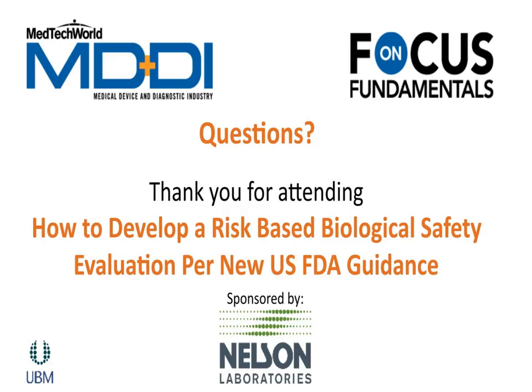Okay, so our next question for you, Audrey, is, I thought Thor said that changes in geometry alone would still require a couple of tests, like sensitization and hemo. Wouldn't this apply to the shorter catheter? That is a great question. So the shorter catheter actually had the same size and shape. It was a balloon catheter. It's exactly the same and same materials.